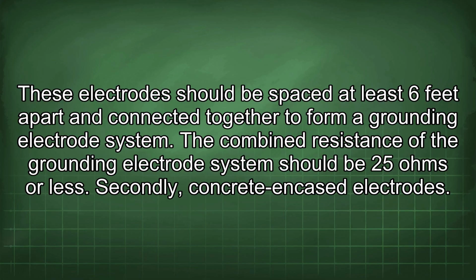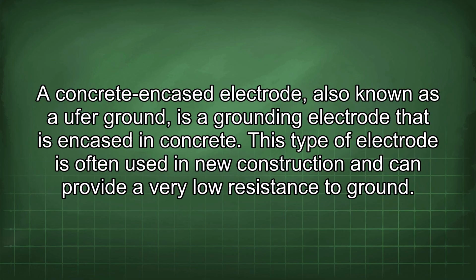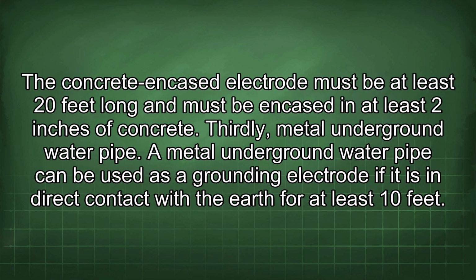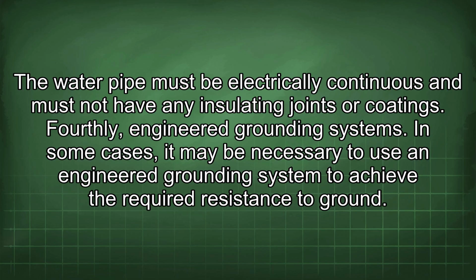Secondly, concrete encased electrodes. A concrete encased electrode, also known as a Ufer ground, is a grounding electrode that is encased in concrete. This type of electrode is often used in new construction and can provide a very low resistance to ground. The concrete encased electrode must be at least 20 feet long and must be encased in at least 2 inches of concrete. Thirdly, metal underground water pipe. A metal underground water pipe can be used as a grounding electrode if it is in direct contact with the earth for at least 10 feet. The water pipe must be electrically continuous and must not have any insulating joints or coatings.